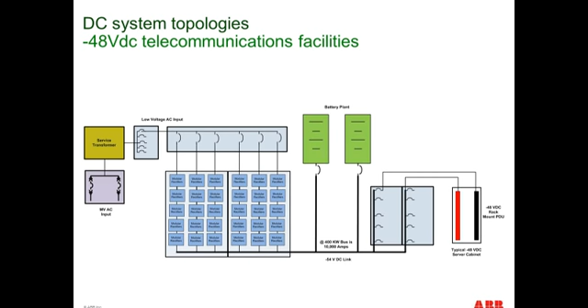And the system has been proven to be incredibly reliable, and it's reliable for a number of reasons. One is the modular nature of the rectifier chargers. Second is the lack of a secondary conversion phase. The batteries are directly charged off of the rectifier chargers. So it's a very, very simple system to understand and operate. Unfortunately, it just doesn't meet the increasing load densities that we're seeing in the data center, and the system doesn't scale well as a standalone system with loads above 400 kW.